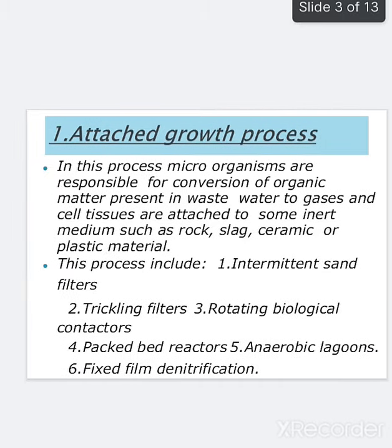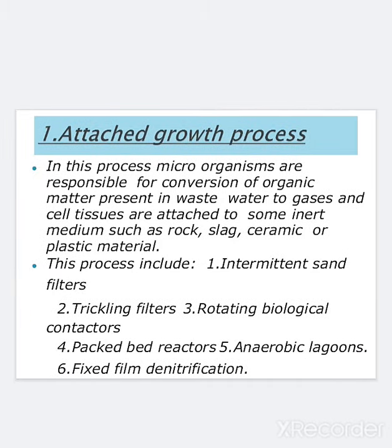is combined. In the attached growth process, the microorganisms responsible for conversion of organic matter present in wastewater to gases and cell tissues are attached to some inert medium such as rock, slag, ceramic or plastic material. This process includes intermittent sand filters, trickling filters, rotating biological contactors, packed bed reactors, anaerobic lagoon, fixed film denitrification.